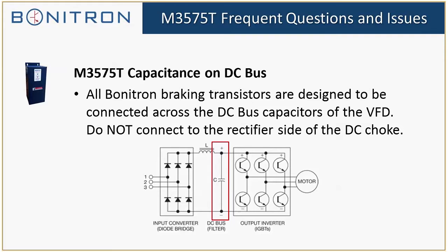All of our braking transistors, as well as our regens, are designed to go across the drive capacitor, marked here and here on this diagram. We like to be directly across the capacitor wherever possible. Often there are pre-charge resistors and things like that built in, which we can't go around. But we definitely should not be on the line side or the rectifier side of any choke, any DC link choke inside the drive.